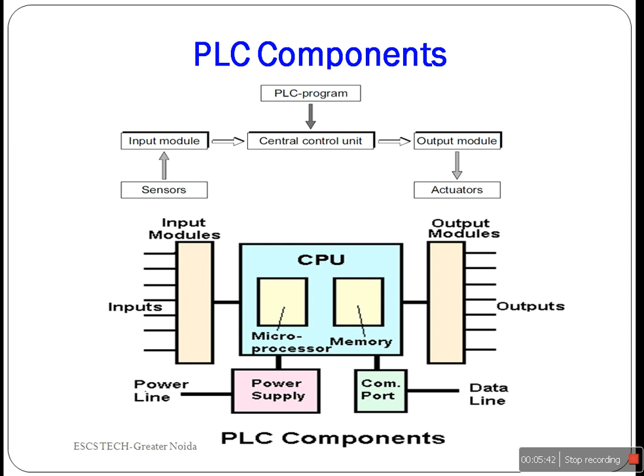There are many trade-offs when deciding which type of input or output cards to use. DC has some advantage over AC, as DC voltages are usually lower and therefore safer, and DC inputs are very fast. AC input requires a longer on time depending on the frequency of the AC input. DC voltage can connect to a large variety of electrical systems.